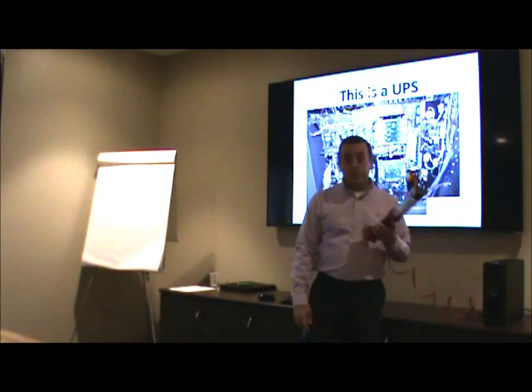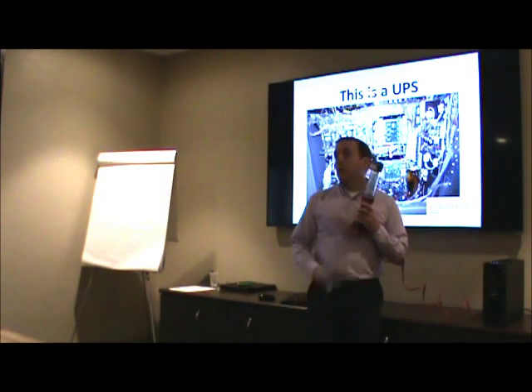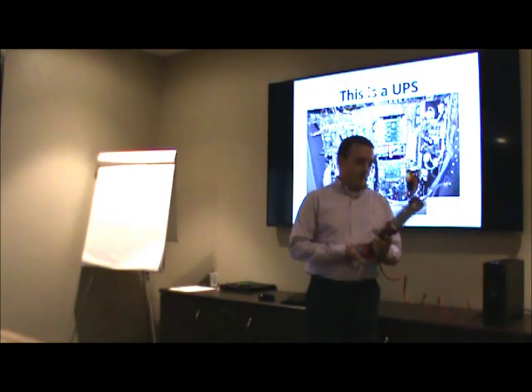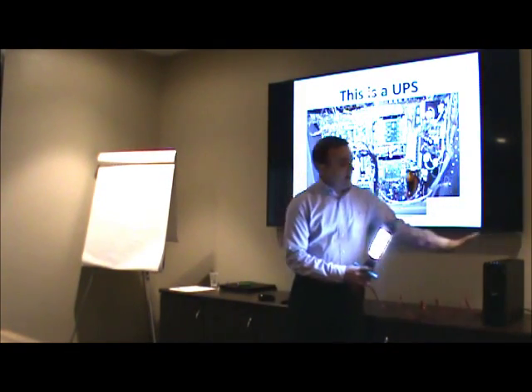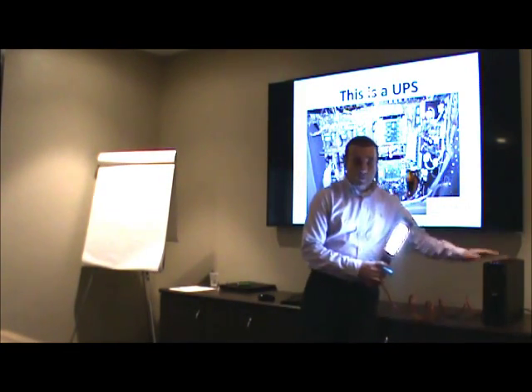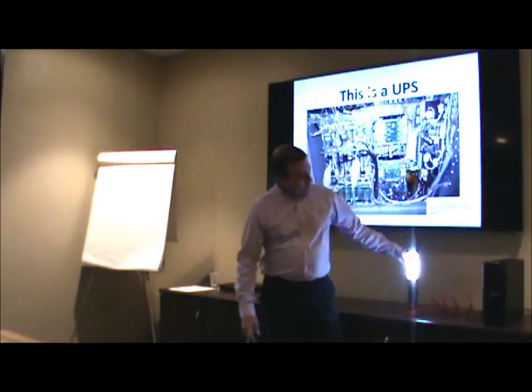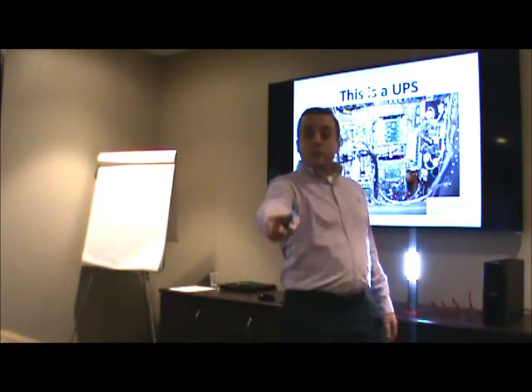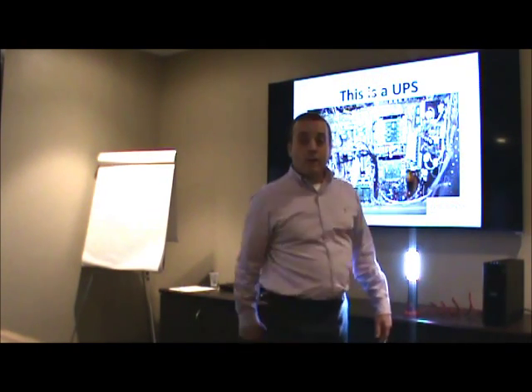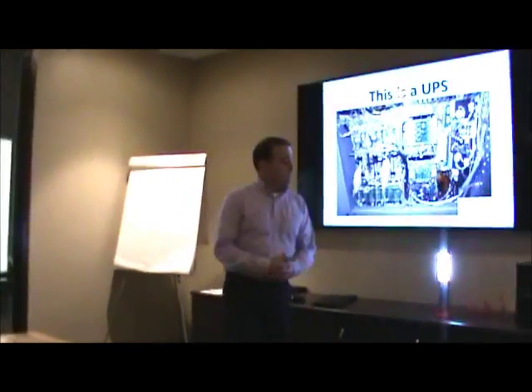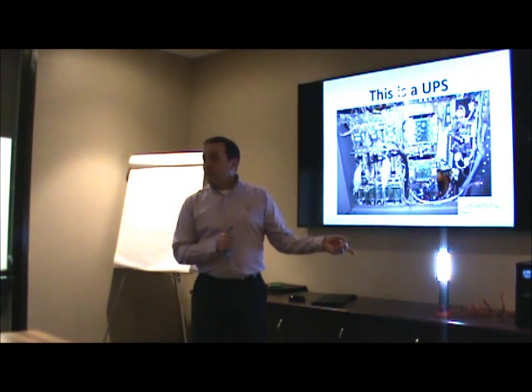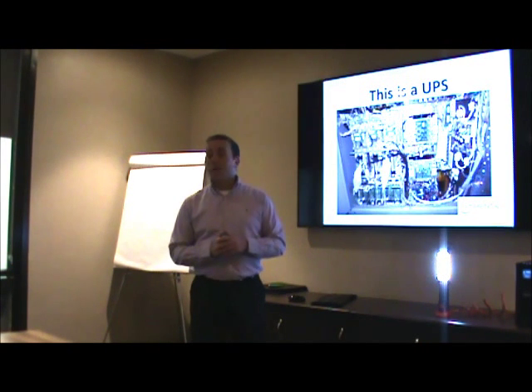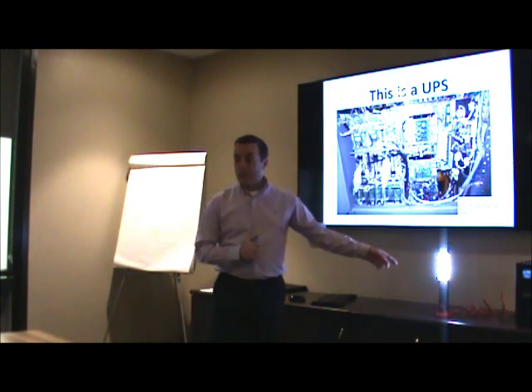For today's demonstration, this is the critical load — this is our computer right here. It's Bob's drop light. As you can see, it's plugged into the back of the UPS system. Everything's fine. Chris, would you mind pulling that yellow extension cord out? You'll hear the UPS fan come on and it'll start beeping, letting you know it lost power. But the light never went out.